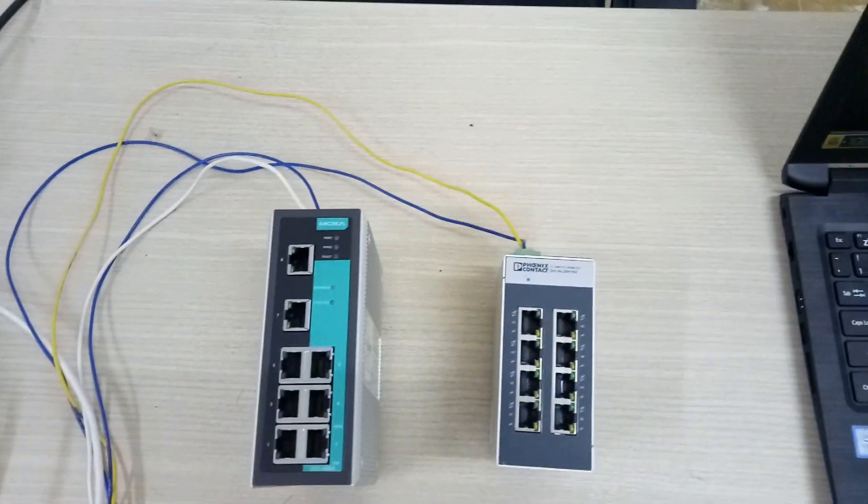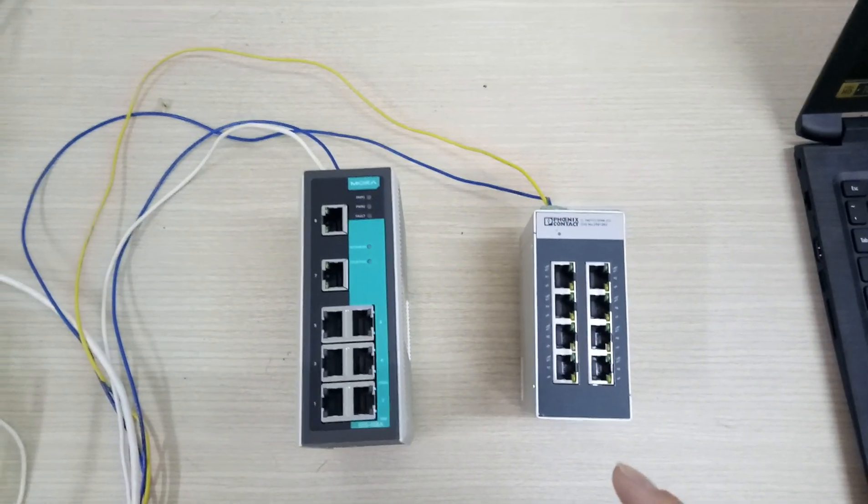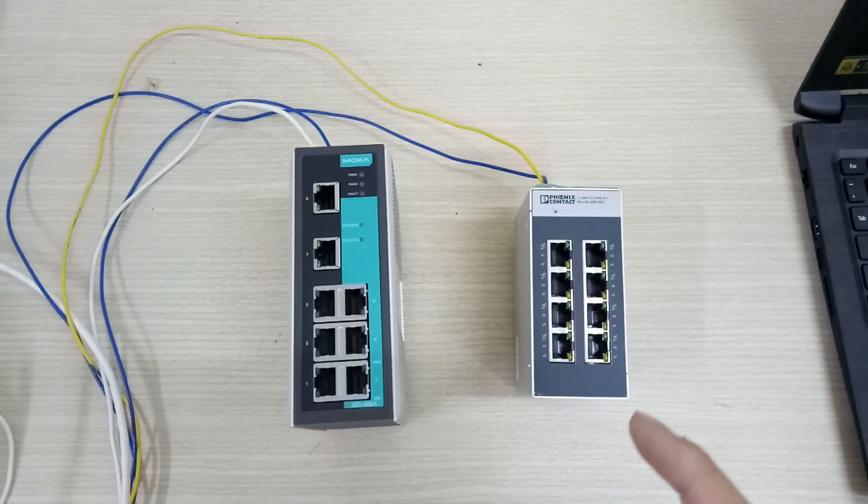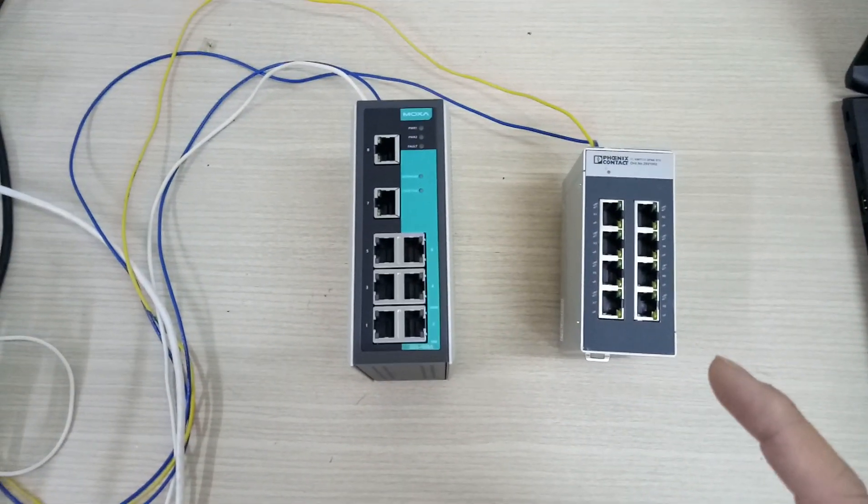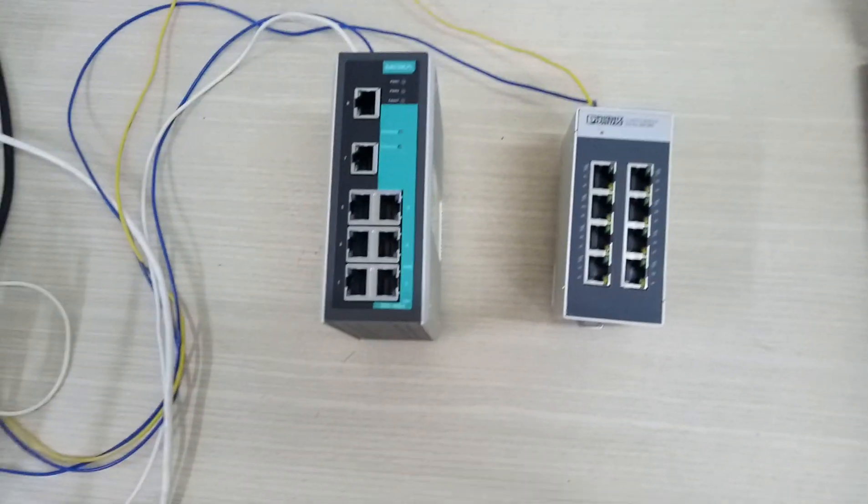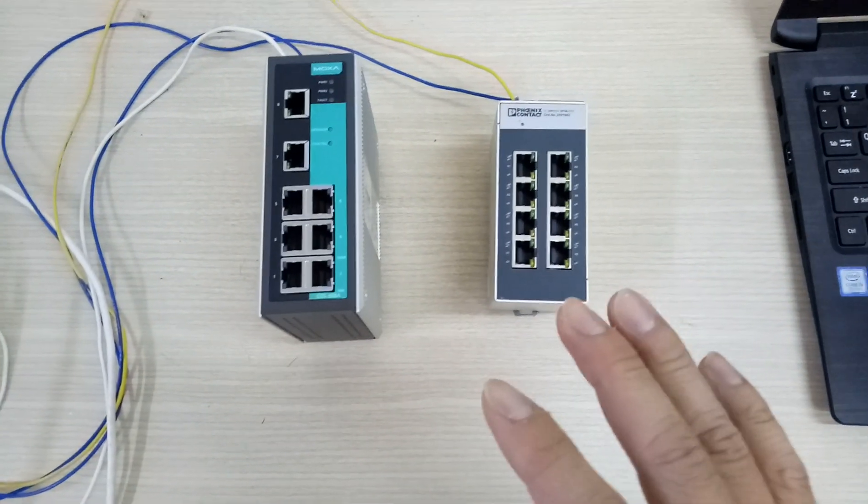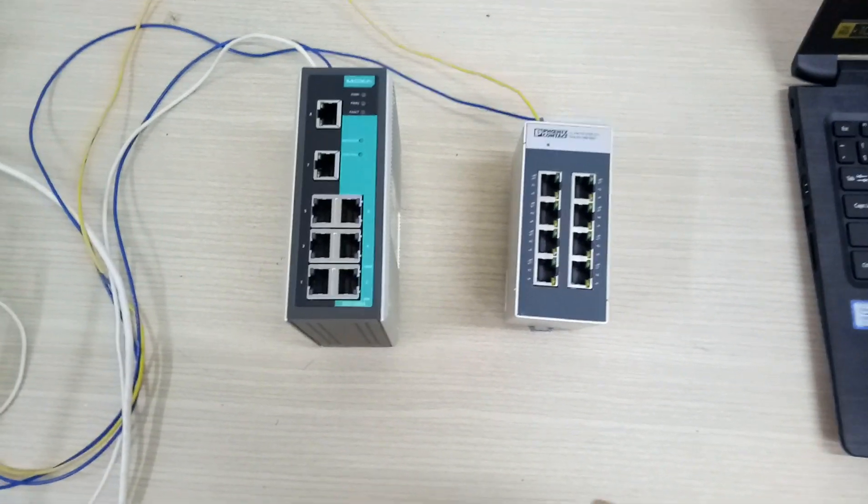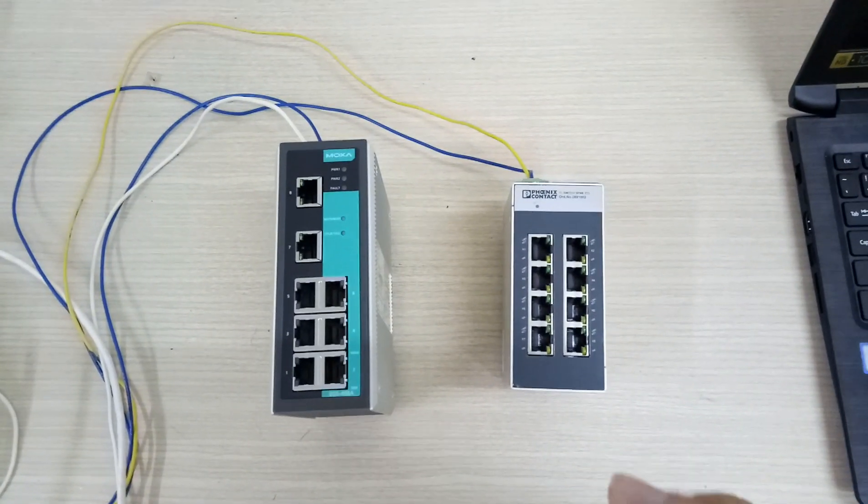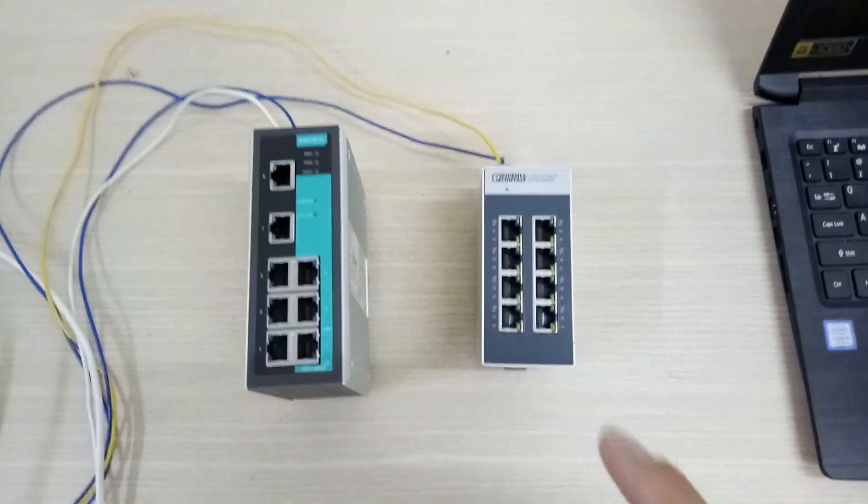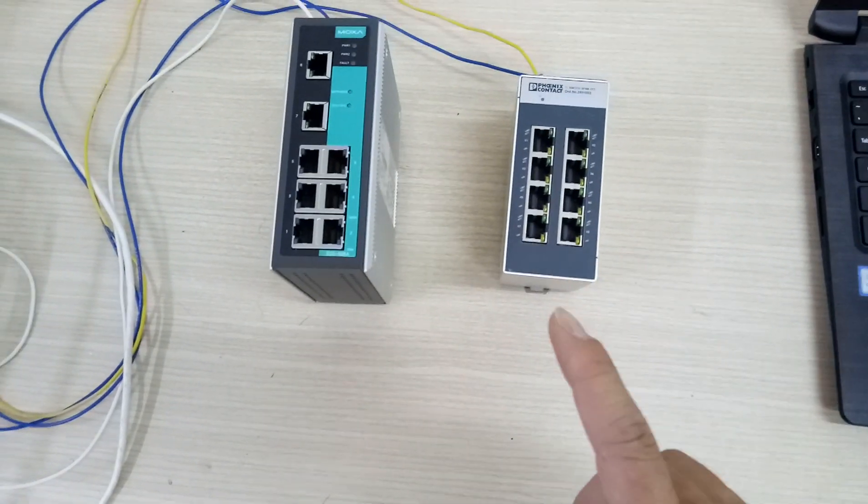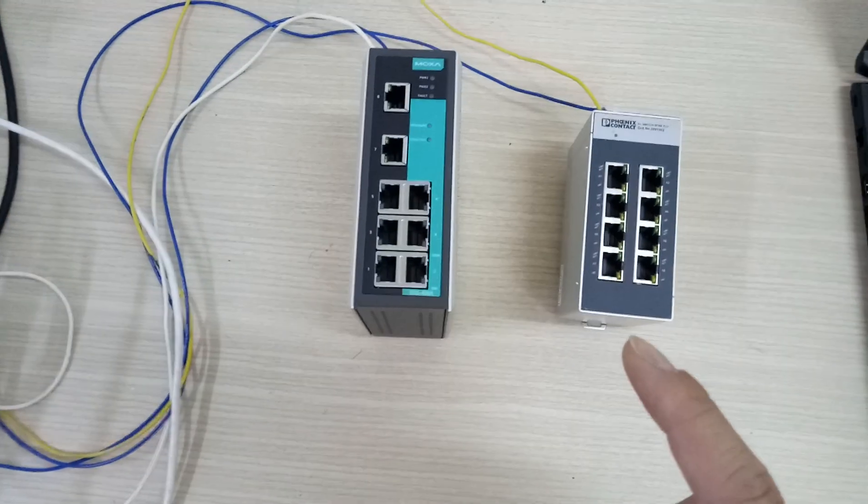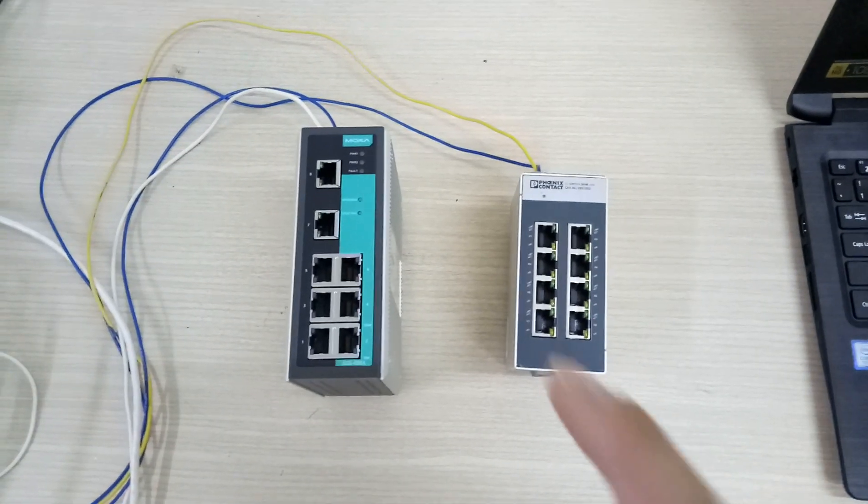The quick answer to the question of why industrial Ethernet switches differ from business switches is that industrial Ethernet switches are built to withstand all these challenges. Business IT switches are cooled by air conditioning in data centers or nestled in a quiet corner of an office where dust is a dirty word. Business IT switches with fans for cooling suck in air and with it dirt or dust particles. To complicate the problem, fans have moving parts and lower mean time between failure (MTBF). Industrial network switches do not have fans. They rely on rugged design to resist heat better and repel dirt or dust.